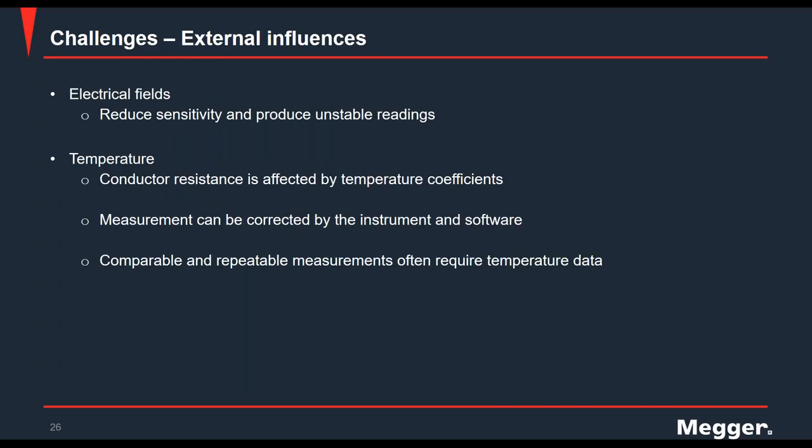Let's look at some external influences that can challenge low resistance measurements. So you have electrical fields that can be generated in the vicinity of your test specimen, and that can reduce the sensitivity and produce unstable readings.